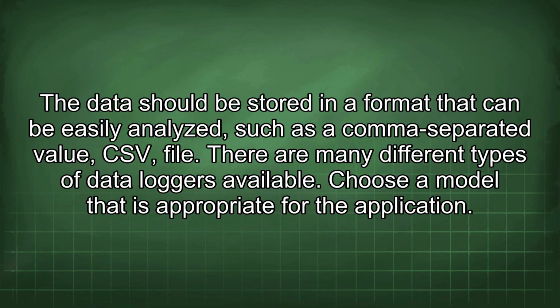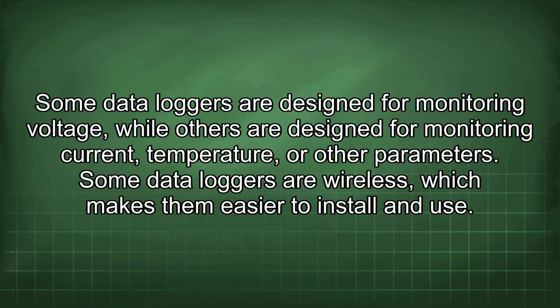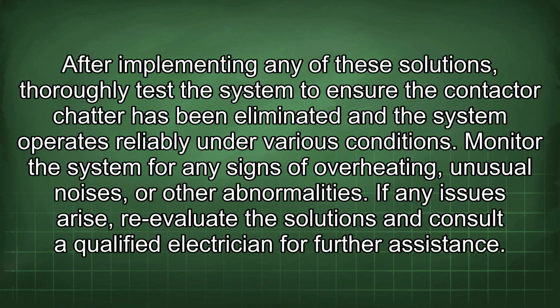There are many different types of data loggers available. Choose a model that is appropriate for the application. Some data loggers are designed for monitoring voltage, while others are designed for monitoring current, temperature, or other parameters. Some data loggers are wireless, which makes them easier to install and use. After implementing any of these solutions, thoroughly test the system to ensure the contactor chatter has been eliminated and the system operates reliably under various conditions. Monitor the system for any signs of overheating, unusual noises, or other abnormalities. If any issues arise, re-evaluate the solutions and consult a qualified electrician for further assistance.